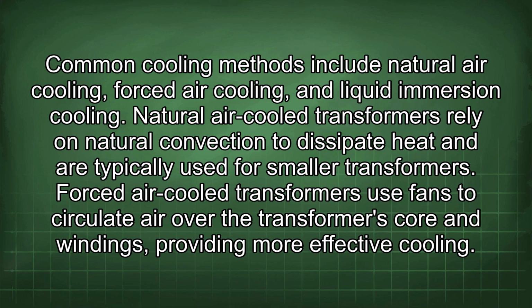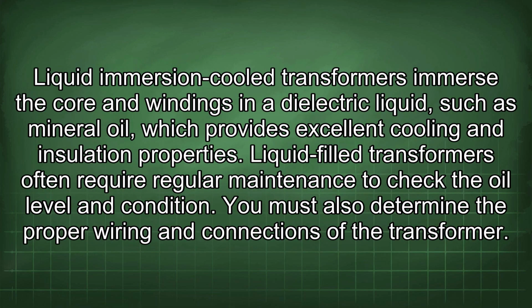Natural air-cooled transformers rely on natural convection to dissipate heat and are typically used for smaller transformers. Forced air-cooled transformers use fans to circulate air over the transformer's core and windings, providing more effective cooling. Liquid immersion-cooled transformers immerse the core and windings in a dielectric liquid, such as mineral oil, which provides excellent cooling and insulation properties. Liquid-filled transformers often require regular maintenance to check the oil level and condition.